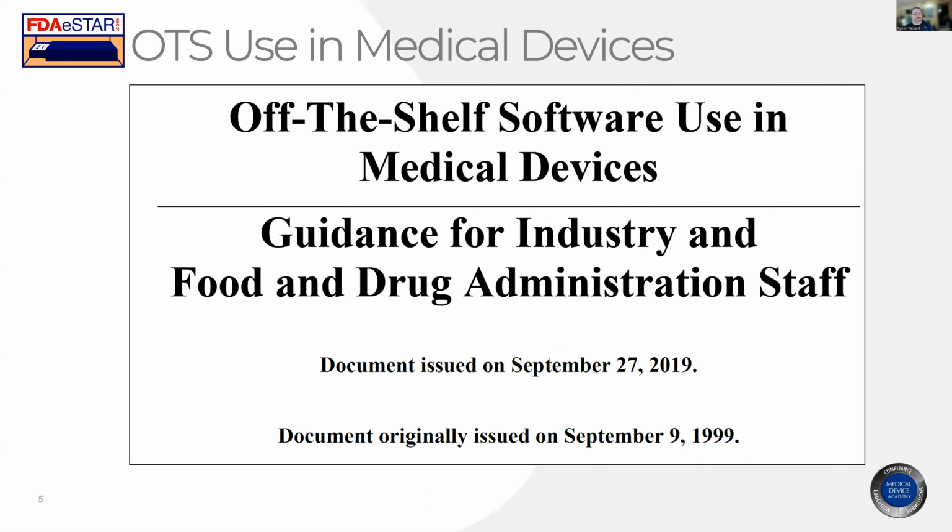Off the shelf software, this is one you definitely do need to pay attention to. This is the 2019 version. They updated it after the old one was 20 years old. We had a company come to us earlier this week that said, we submitted a 510(k), the FDA gave us a deficiency list during the AI hold, and the software developers we're working with are saying the FDA requirements for cybersecurity are so ridiculous, there's no way this software will ever pass if it has Microsoft Windows as the operating system. That's not true.